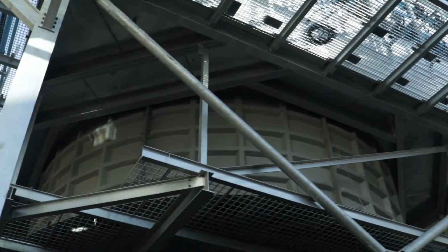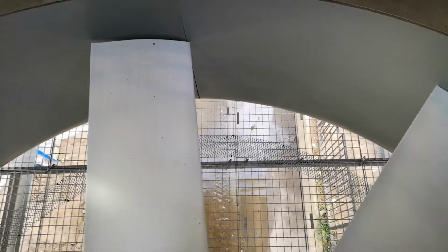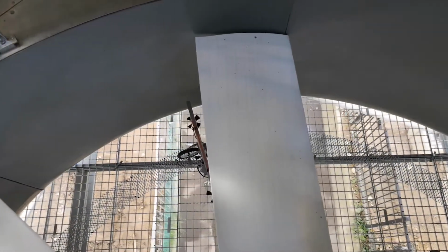On the one hand, we wanted to conduct aerodynamic optimization of a fan, so we wanted to create a really optimal fan for the specific design point that it was going to operate at. On the other hand, we also wanted to work on the structural side. So the second part of the design criteria was to design a fan that was structurally strong enough to endure ordinary operation that the fan will experience. But in addition to that, we also wanted the fan's natural frequencies not to coincide with operating frequencies on site. We did static testing and we saw that the variance was, I think, less than 0.5% in terms of the natural frequency modes. And then for both of them, they were, I think, more than 10% away from any of the operating frequencies.